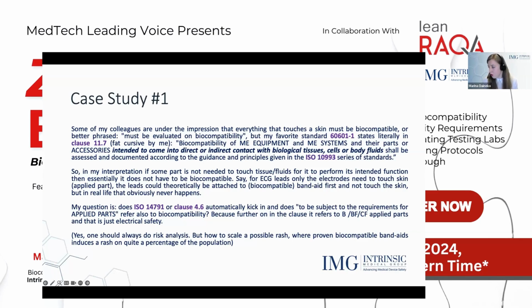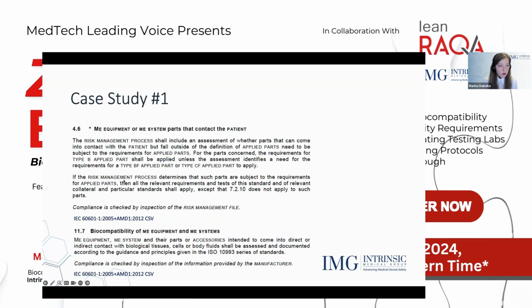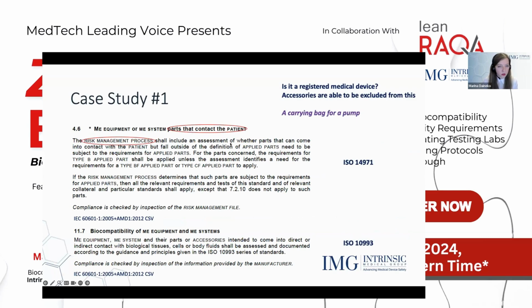So let me just show you these clauses, how they look in the standard. Here, once more, it is mostly about risk management and applying risk management to parts that contact the patient, as well as being very specific about biocompatibility of medical electrical equipment and systems. First of all, we need to understand whether it's a registered medical device, whether it's a medical device itself. Then we need to understand whether we have, for instance, accessories, because there is a kind of Pandora's box of tricky questions with accessories. They can be excluded from biological evaluation altogether, because they can be not part of the medical device and not even influence the medical device's functionality. And when they are excluded, we shall not do biological evaluation, for instance, for accessories. The example you may see in violet is a carrying bag for a pump.